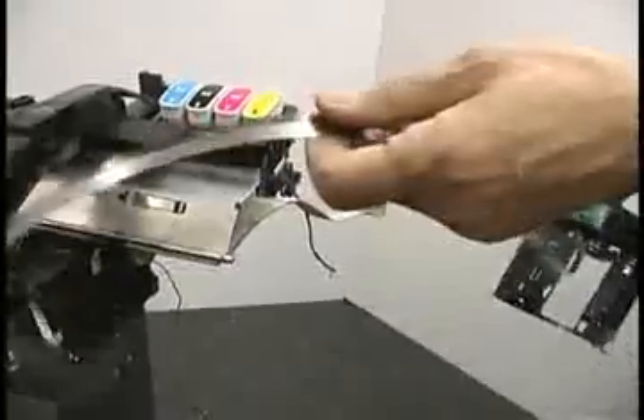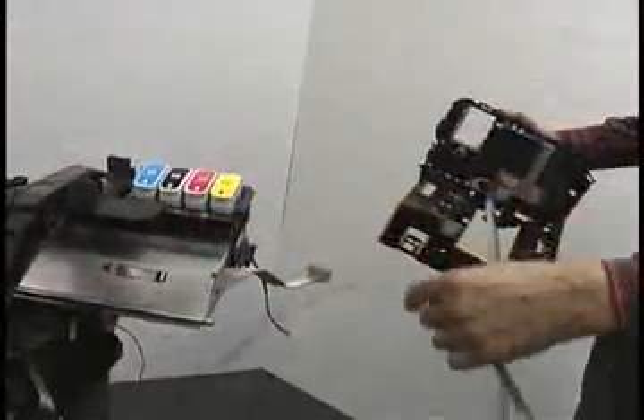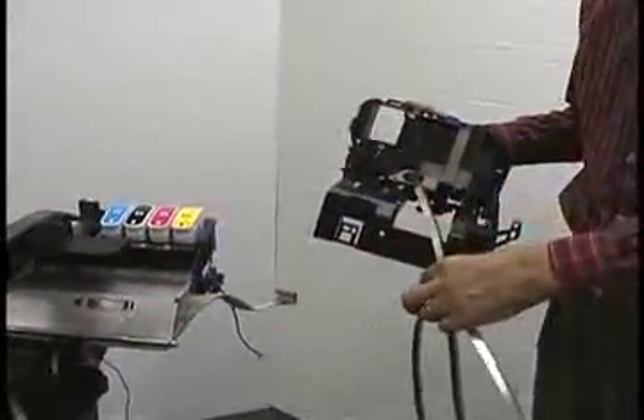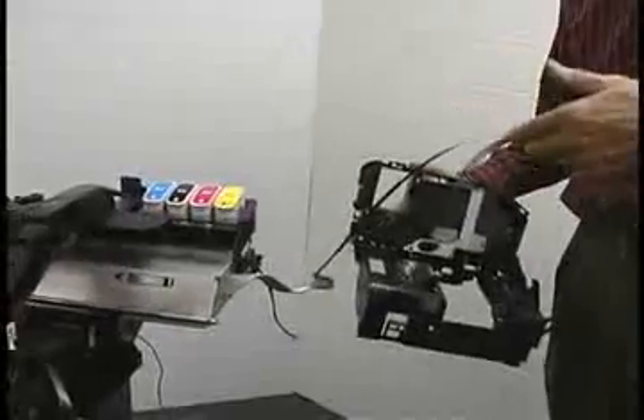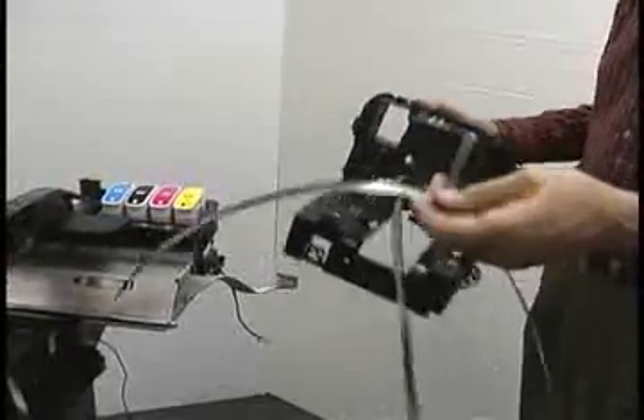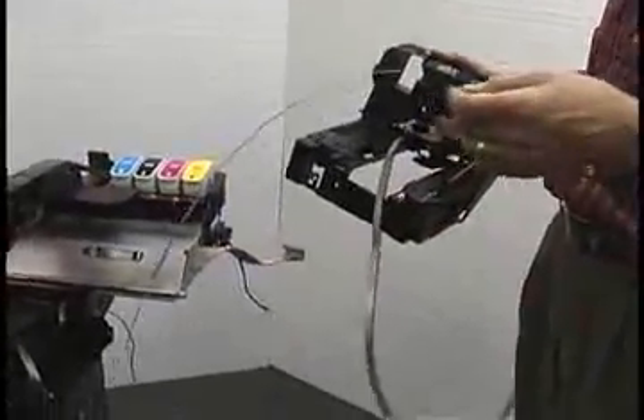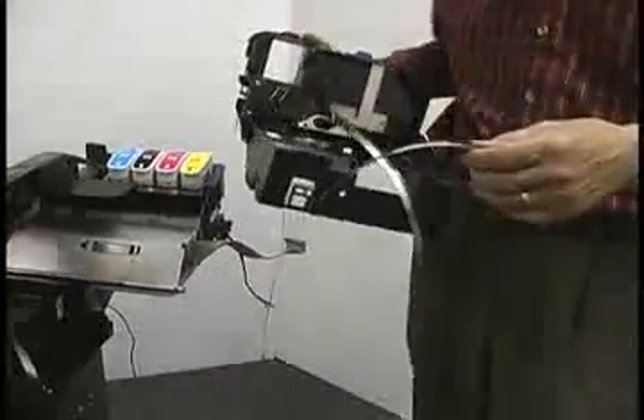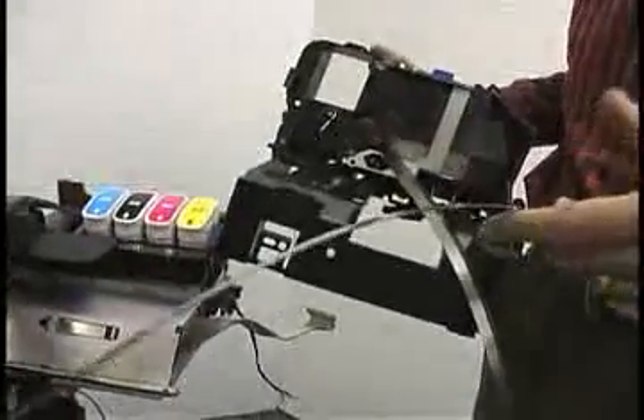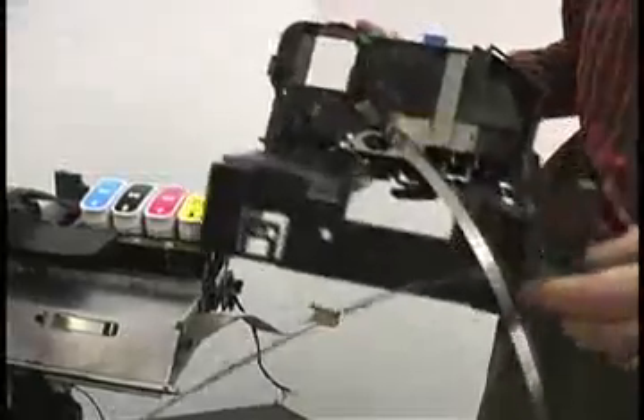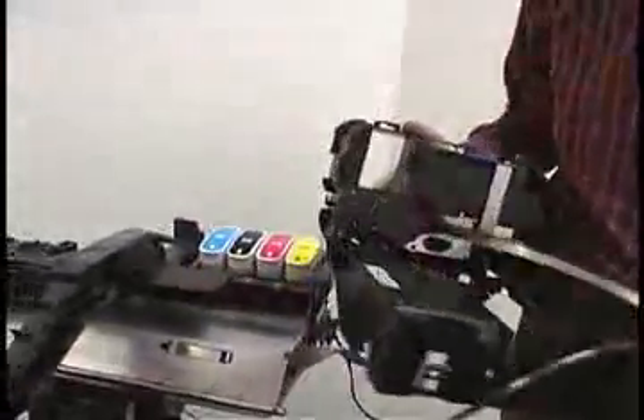Now the encoder strip is fairly tough, but you don't want to bend it or crimp it or anything like that. It's a good idea to clean the encoder strip with a soft cloth and warm water while you've got it out, and put it back in. Don't use detergent or Windex on this. There's real fine lines printed on here, and the detergent, especially Windex, will take the lines off, in which case you get to replace the encoder strip, because it won't be any good after that.